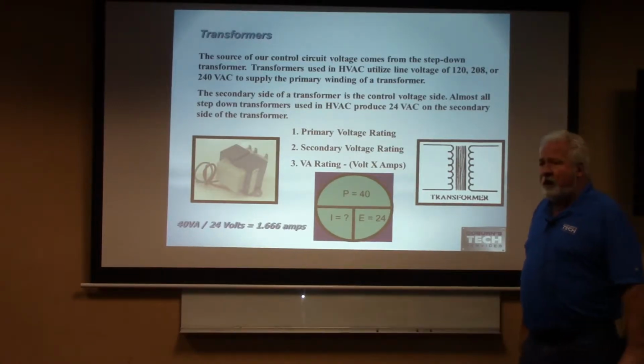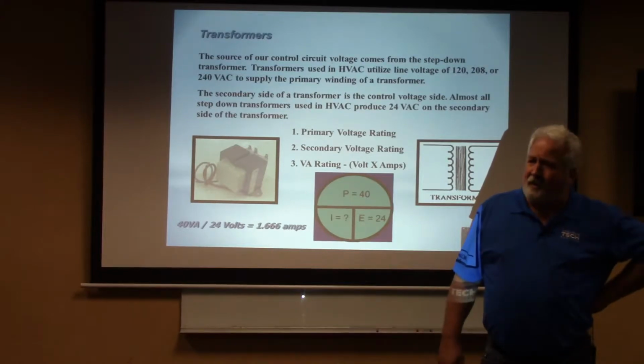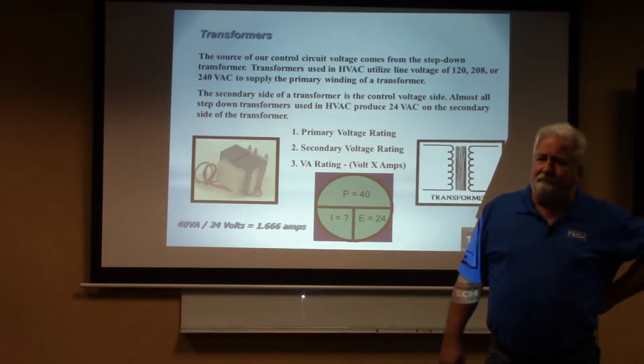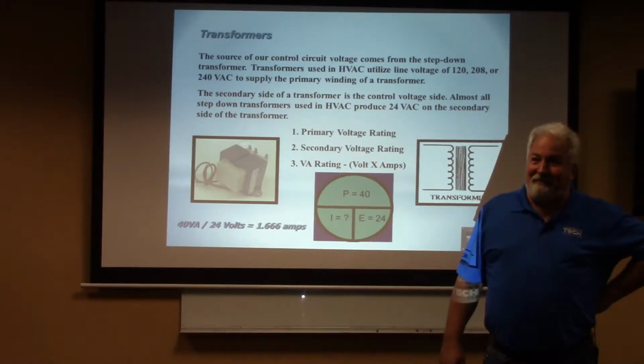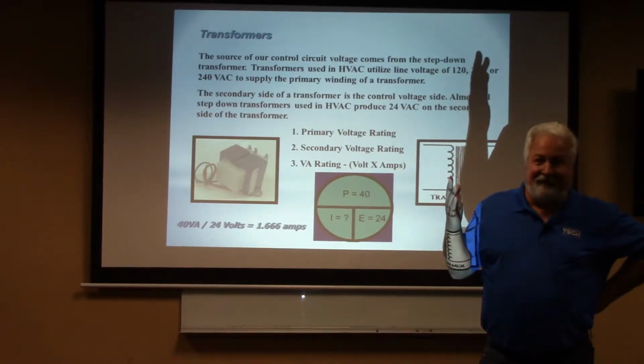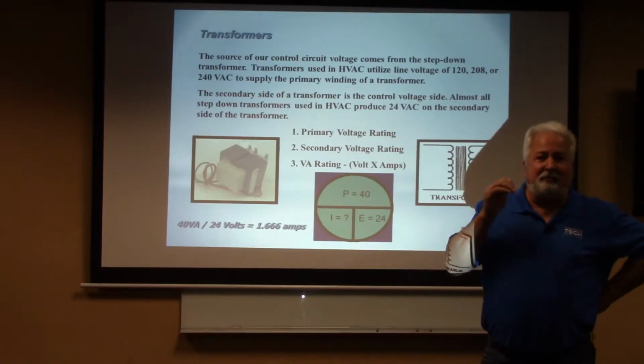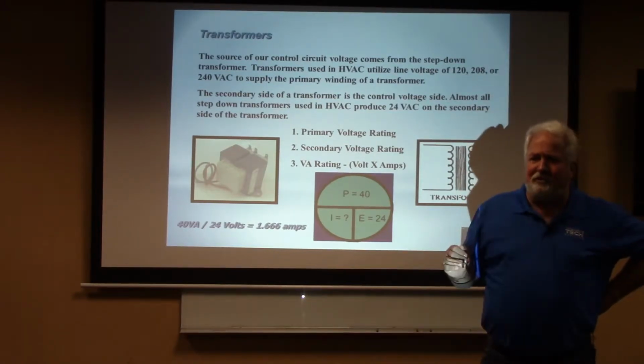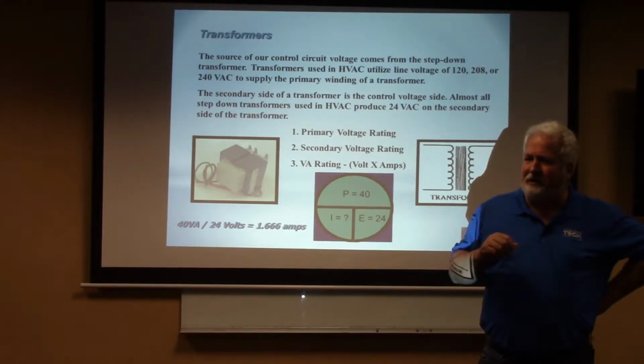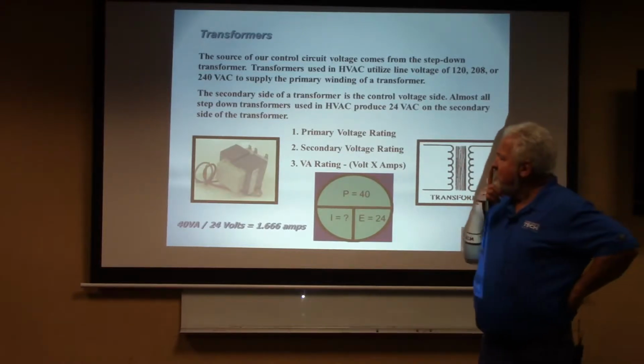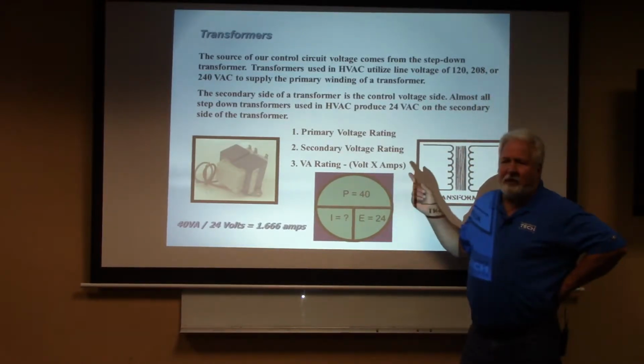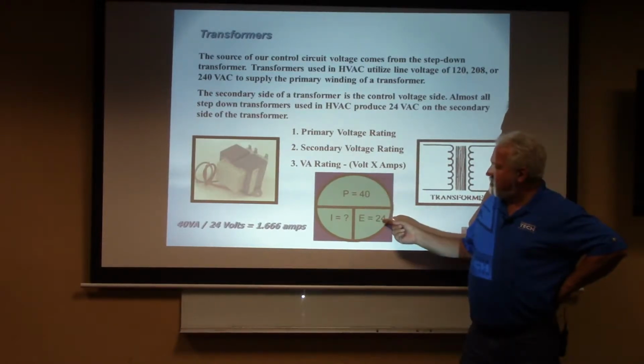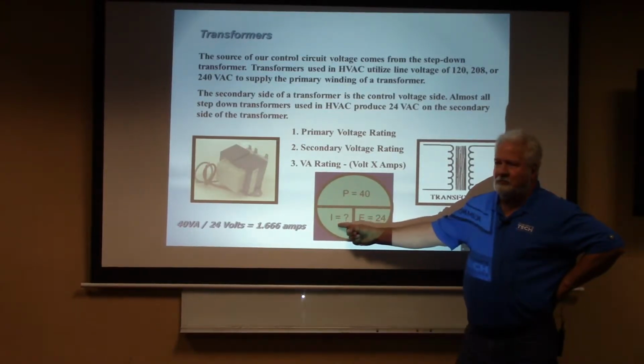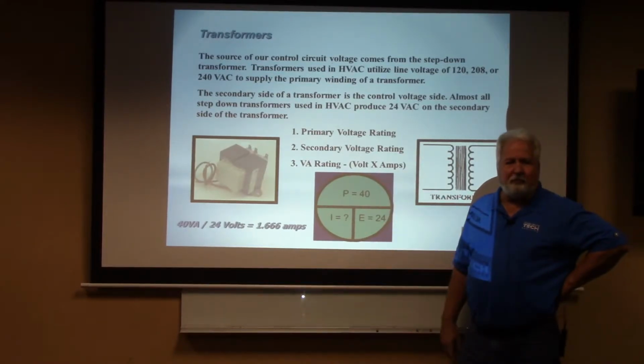But so, how many times have you changed a transformer because it's burnt? Put the new transformer in there, and then we wait to see what? If the smoke comes out, is that right? That's how we've learned this stuff. Plug it in, wait for the smoke to come out. If the smoke comes out, it doesn't work anymore. Is that right? Oh, wow. Wouldn't it be nice to be able to check it right when we turn it on to see if it's going to burn, and then be able to turn it off if we see high amperage or something? Wouldn't that be nice? Okay, so let's do that. If I knew that my VA rating was 40 and my transformer output voltage was 24, what would be the amp draw at maximum for that transformer?